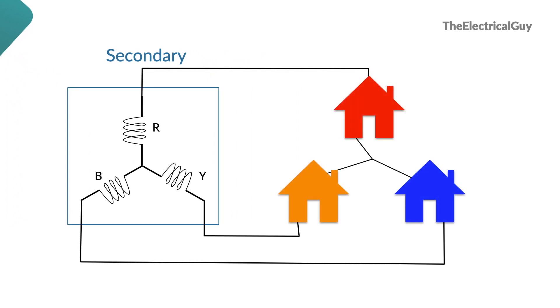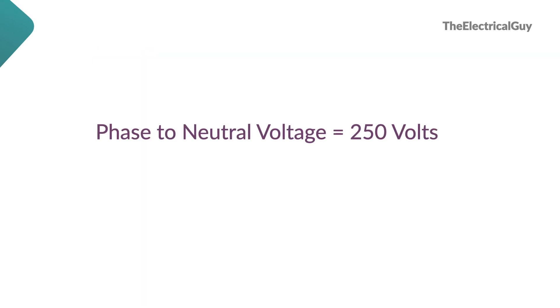When the load is not balanced on all phases, sum of return current will not be zero. This is where we need neutral wire. The job of neutral wire is to carry the unbalanced current and help keep the phase-to-neutral or phase-to-phase voltage constant. In our case, let's say phase-to-neutral voltage is 250 volts and phase-to-phase voltage is 433 volts. You will get this voltage even if the load is unbalanced when neutral is there.